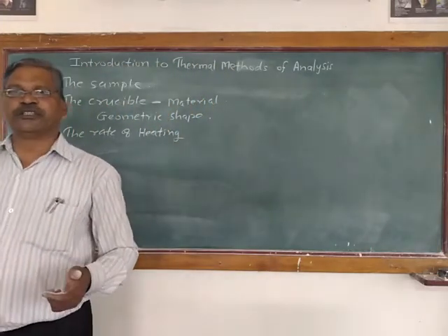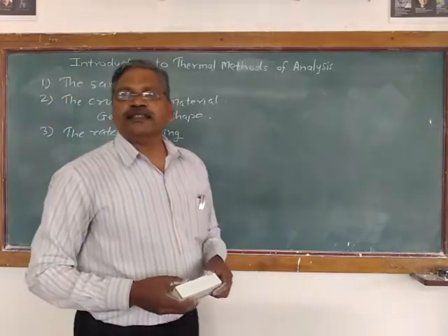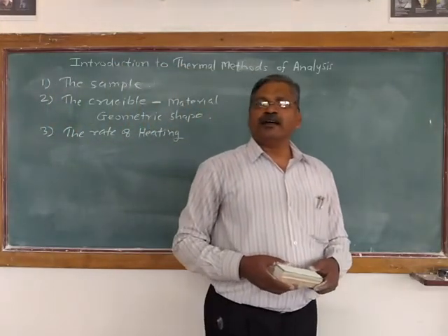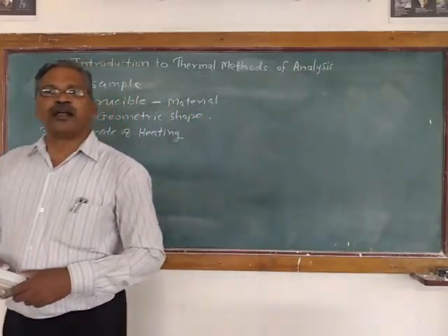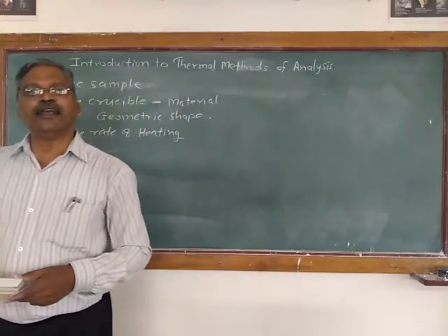For example, one can do the thermal analysis isothermally at 25 degrees Celsius for 2 minutes. After that, the heating rate can be changed to 50 Kelvin per minute, and maintained up to 300 degrees Celsius.